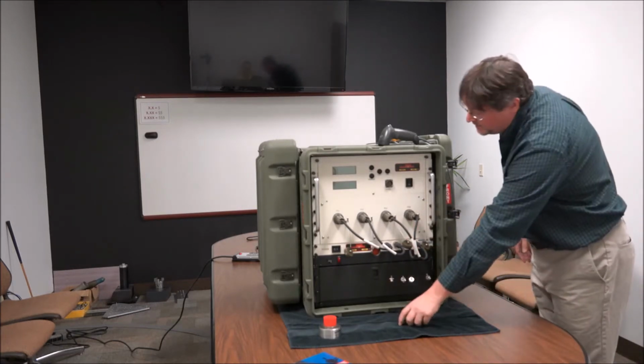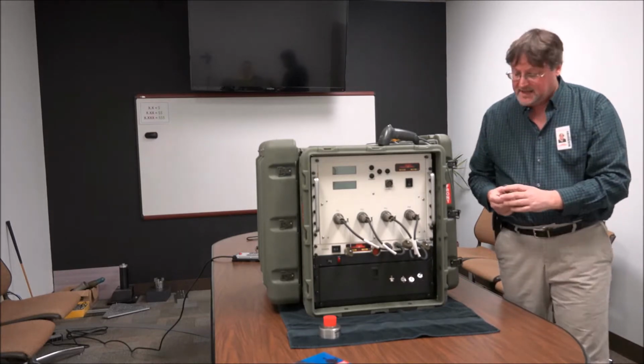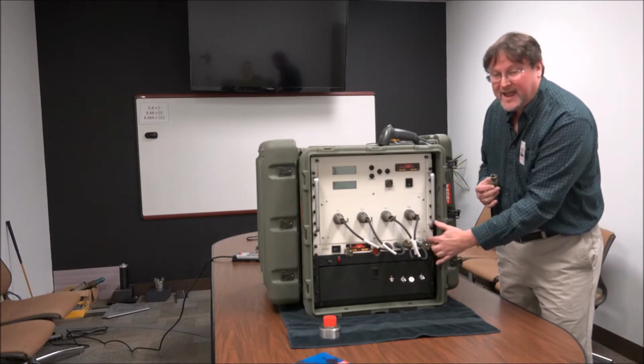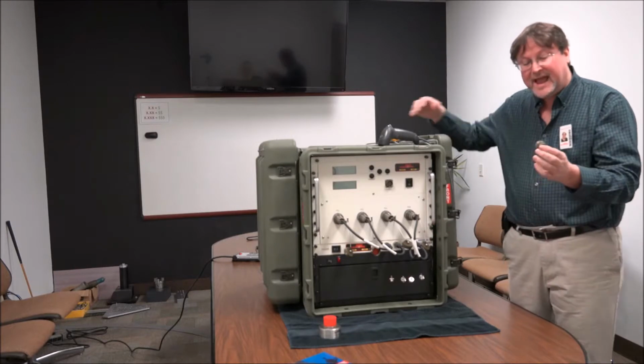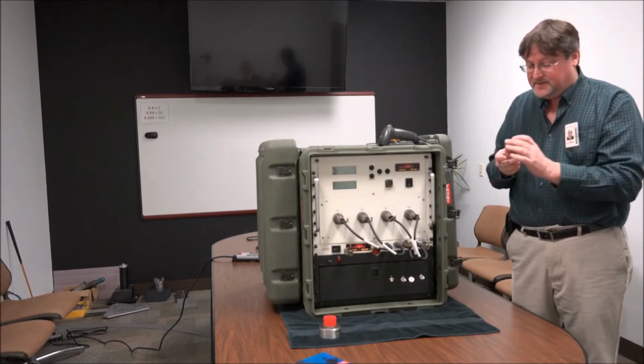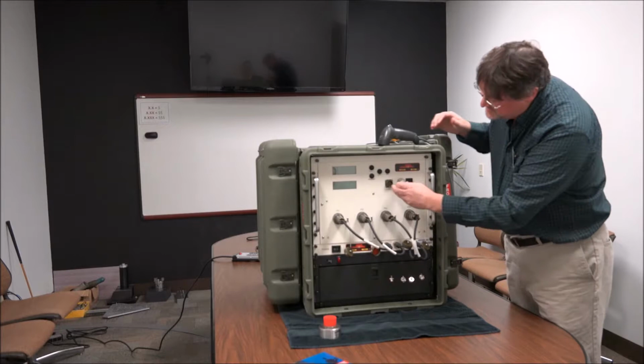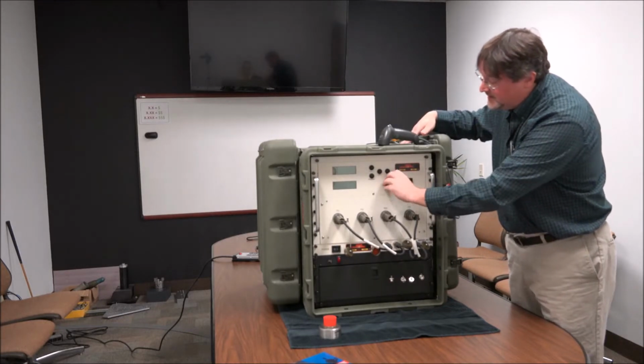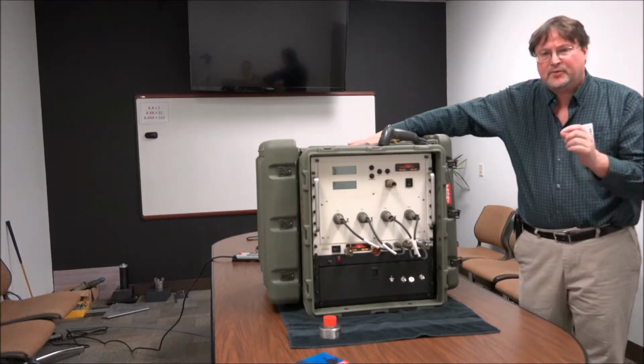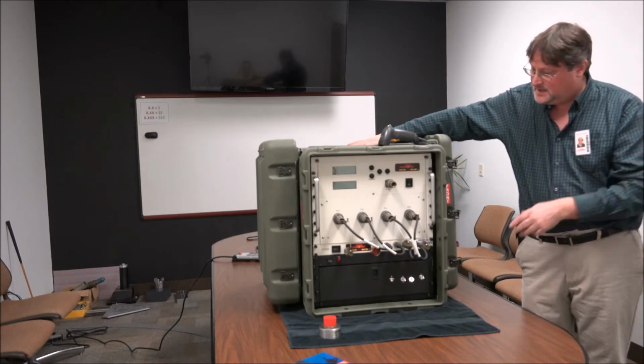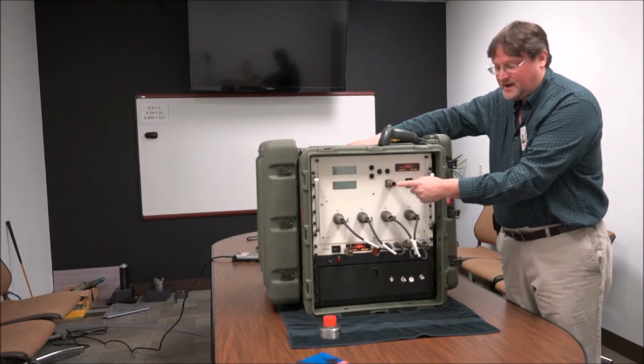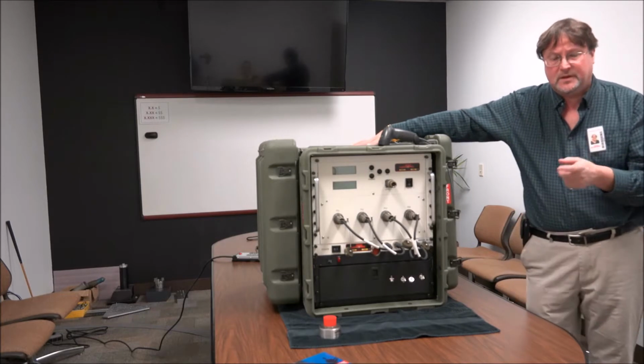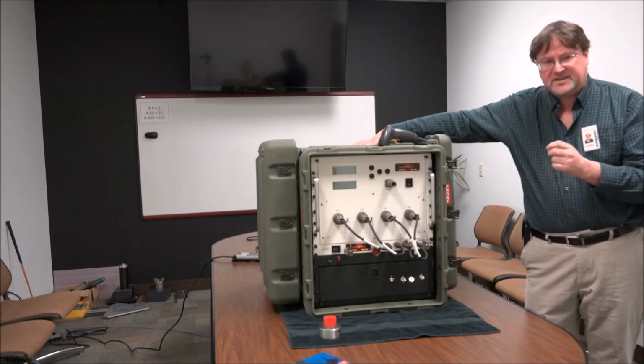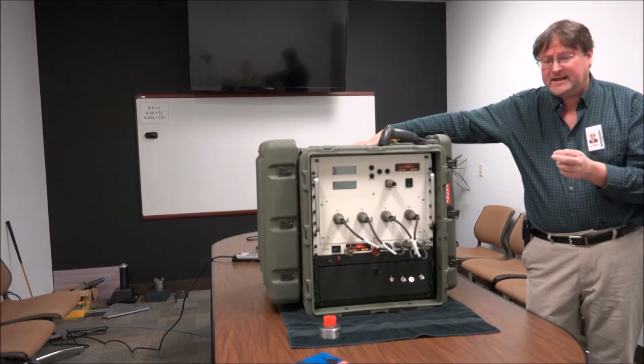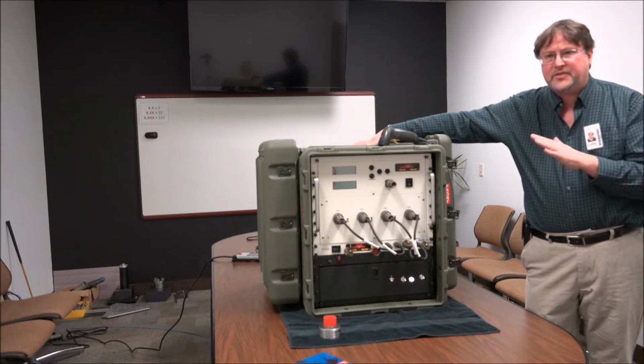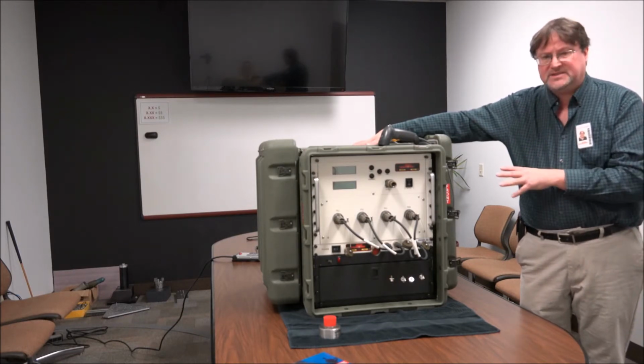And then lastly, we also have a feature for self-test. If you don't have this tester, or if you do, we still have a verification plug. This plug is mounted into the manual location. And during automatic tests, prior to every test sequence, it takes readings off of this. That serves two purposes. One is to verify that the channels are functioning properly, and the second is to get the zero at the thermal that you're exposing the system to.